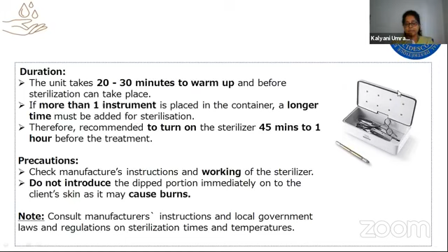As they say, the unit takes 20 to 30 minutes to warm up before sterilization can take place. So any glass bead sterilizer you're going to use is going to take 20 to 30 minutes to warm up before the actual process of cleaning starts. If more than one instrument is placed in the container, a longer time must be added to the sterilization. Why? Because it's going to take time to sterilize each and every instrument. Therefore, the recommendation is to turn on the sterilizer for 45 minutes to 1 hour before the treatment. So whenever you reach the salon in the morning, you can just put it on while you're getting ready or while your cleaning is going on. You need to train your people accordingly. It will just get heated and you can place the equipment in it once it is properly heated.